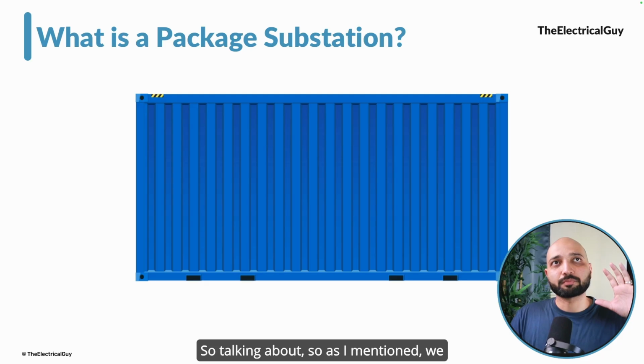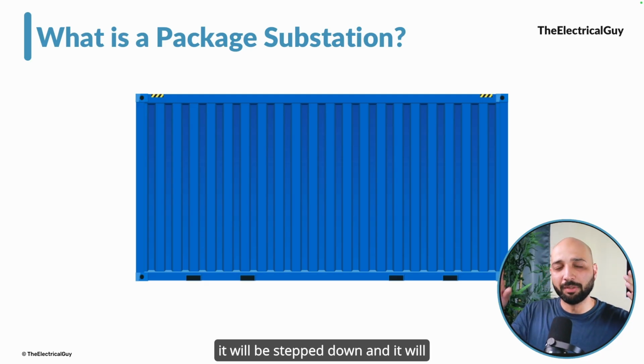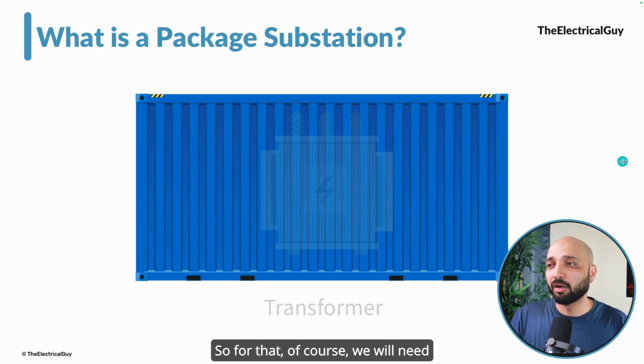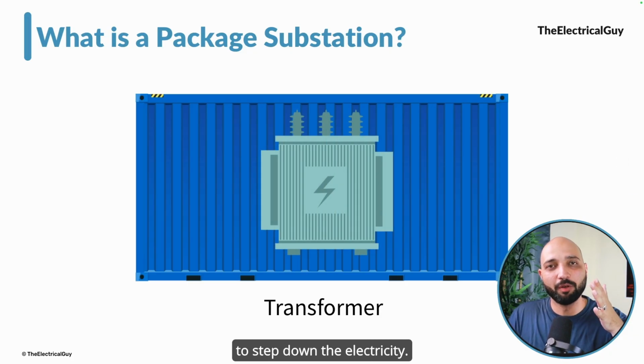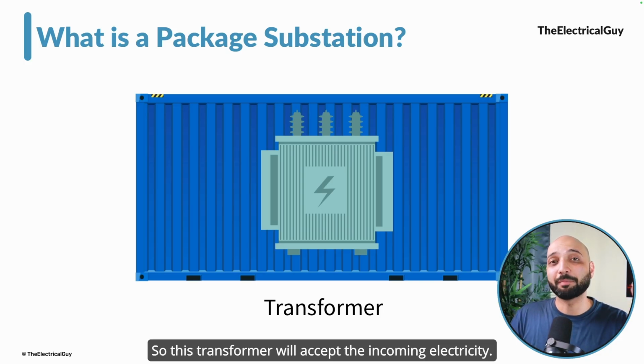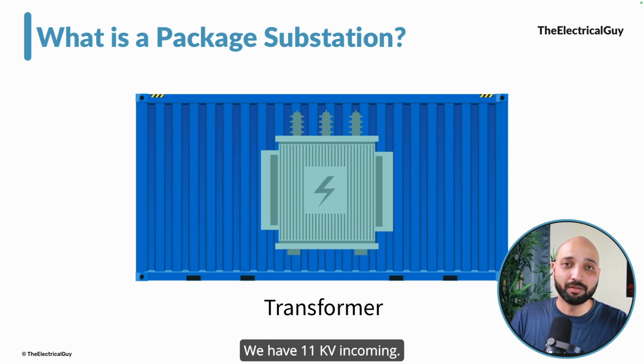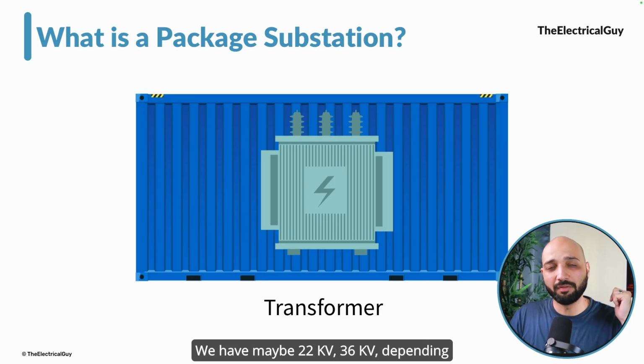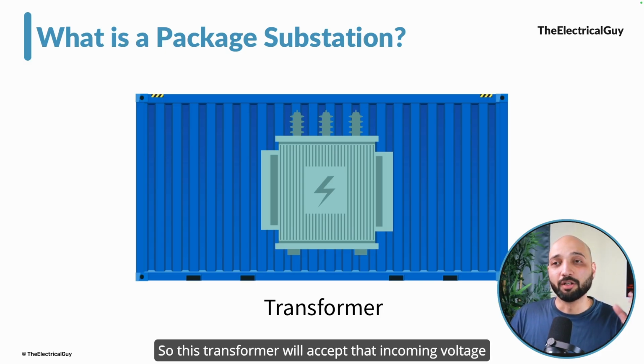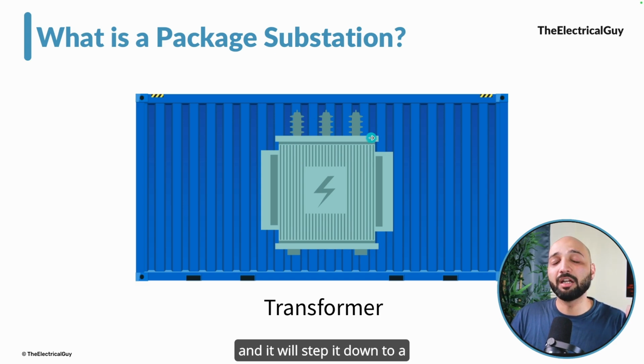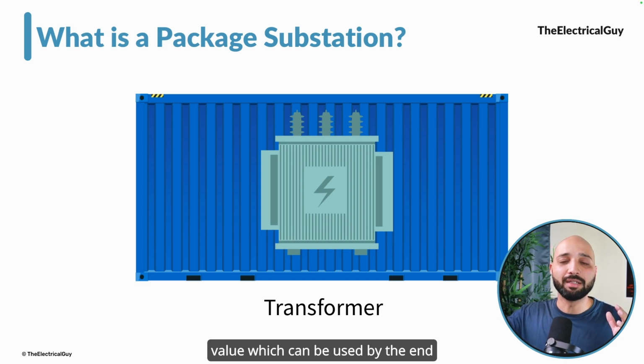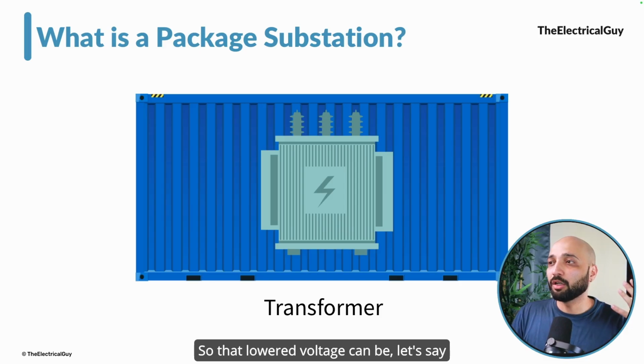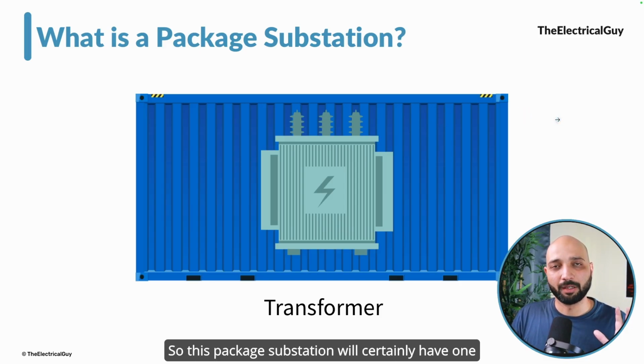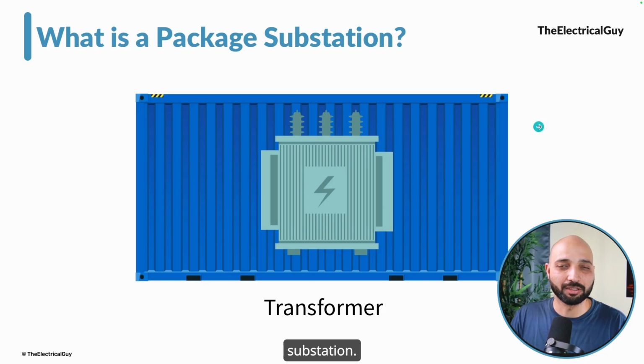As mentioned, medium voltage comes in, gets stepped down, and is given to the different loads. For that, we need a transformer - without it, we can't step down the electricity. This transformer accepts the incoming electricity, which could be 11 kV, 22 kV, or 36 kV depending on the country. The transformer steps this down to a value usable by end consumers like residential areas, small commercial zones, or industrial areas - for example, 400 volts. So this package substation will certainly have one transformer, and that's the mandatory component of this substation.